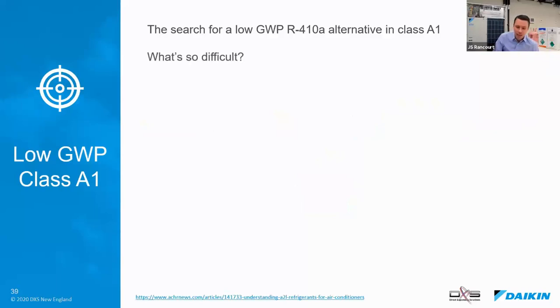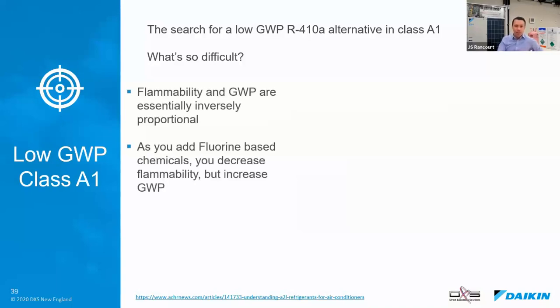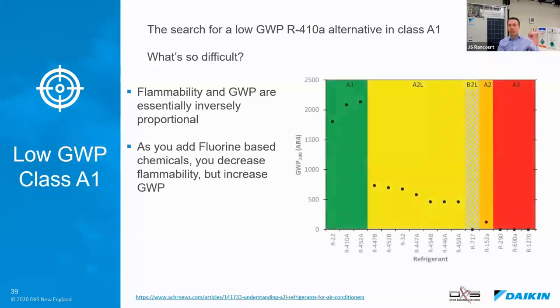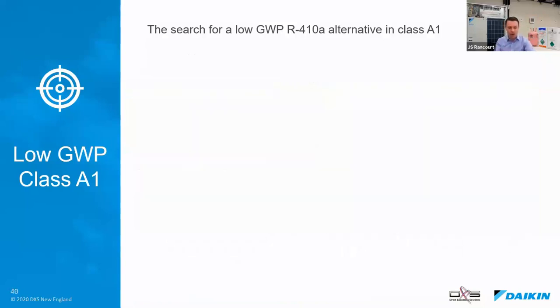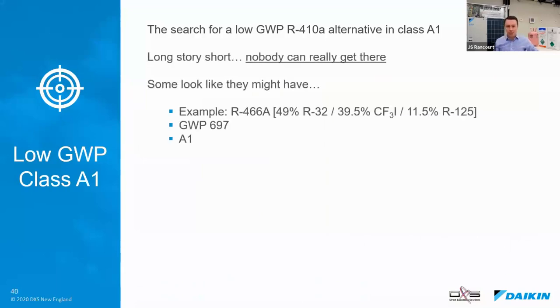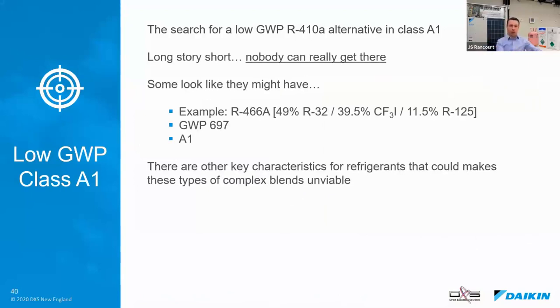So what is the challenge in finding a low GWP A1 refrigerant? Well, go figure, flammability and GWP are essentially inversely proportional. It has to do with the fluorine atom found in most of these fire suppressants. Here's a nice little graph showing you GWP of refrigerants based on their refrigerant classification. Right away, you can see that all these A1 refrigerants are in the 2000s for GWP. And if you want to get within that California 750 limit, you have to go to the A2L category. So essentially, long story short, nobody's been able to find an A1 refrigerant with low GWP.